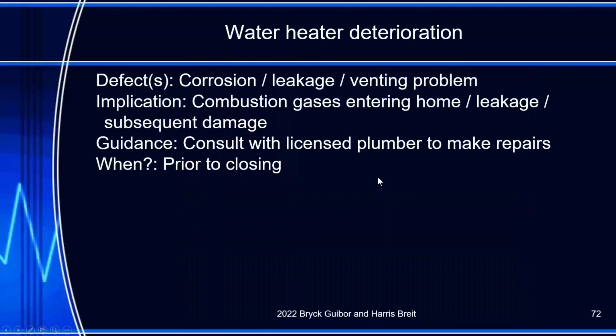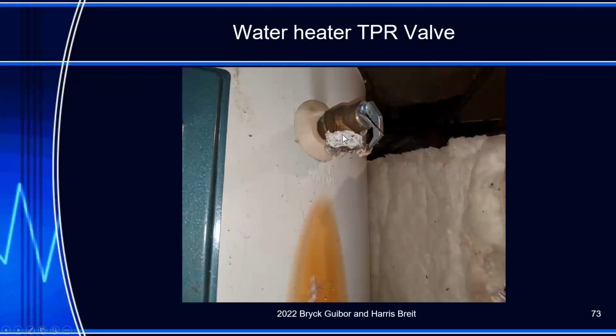So this water heater looks like it's toast. So we'll move on. There's some leakage around, and the drain is missing. But look at this. Look right down here. Do you see the stain it's making on the side of the water heater? I don't know about you, but when I do an inspection and I say, this has been leaking a long time, it's making a rust stain here, they don't believe me. They go, well, this white calcium here, what is that? And then here's the stain where it's been dripping down against the side of the water heater.